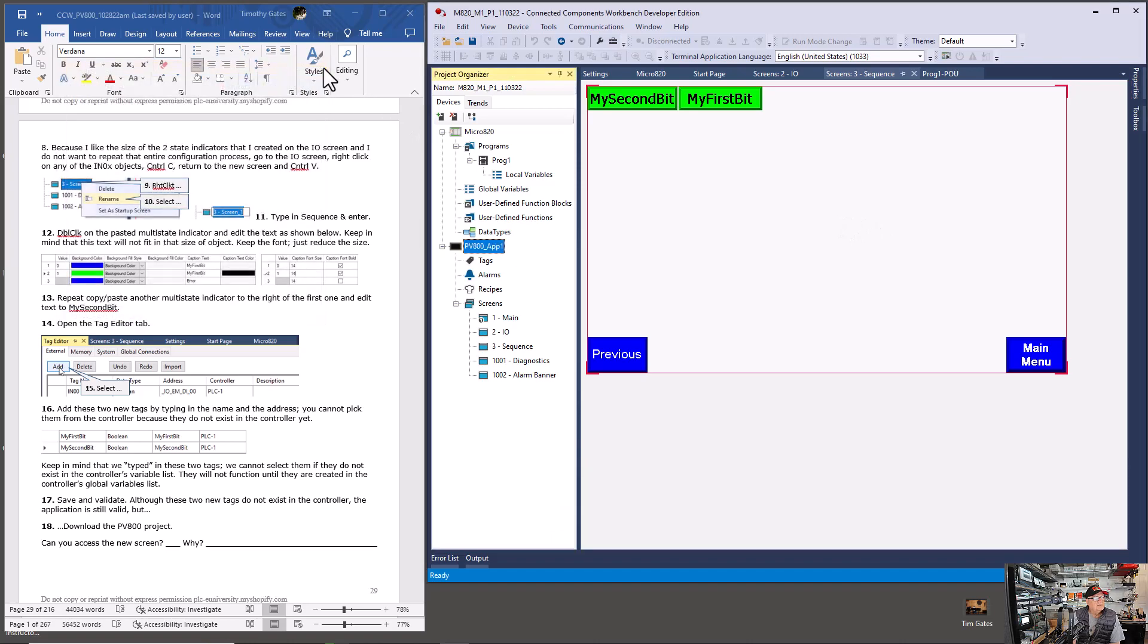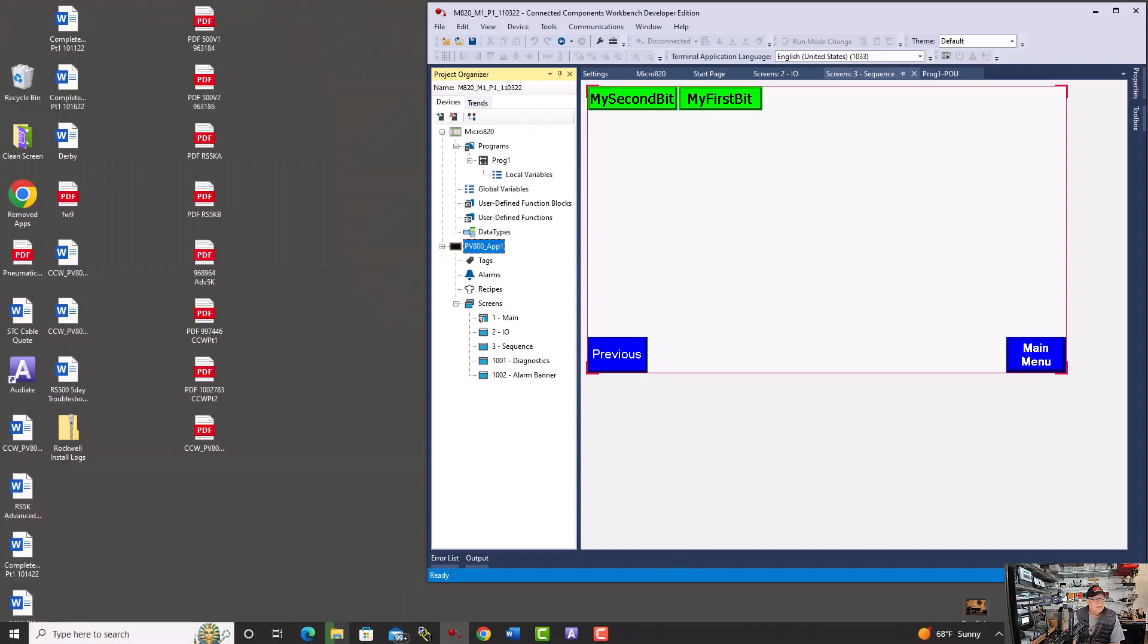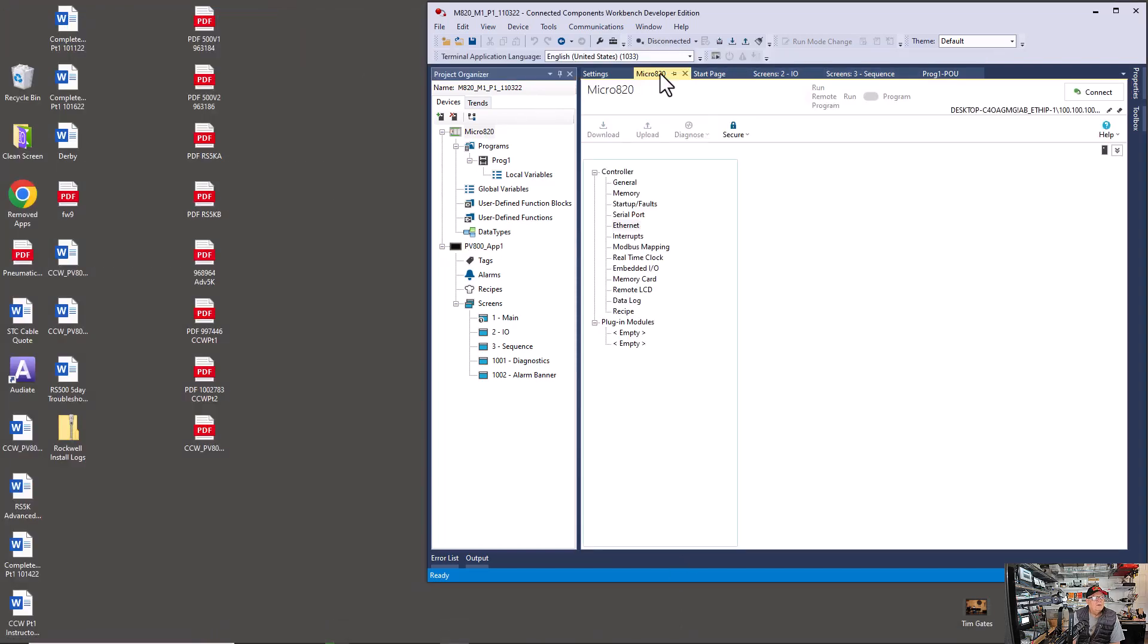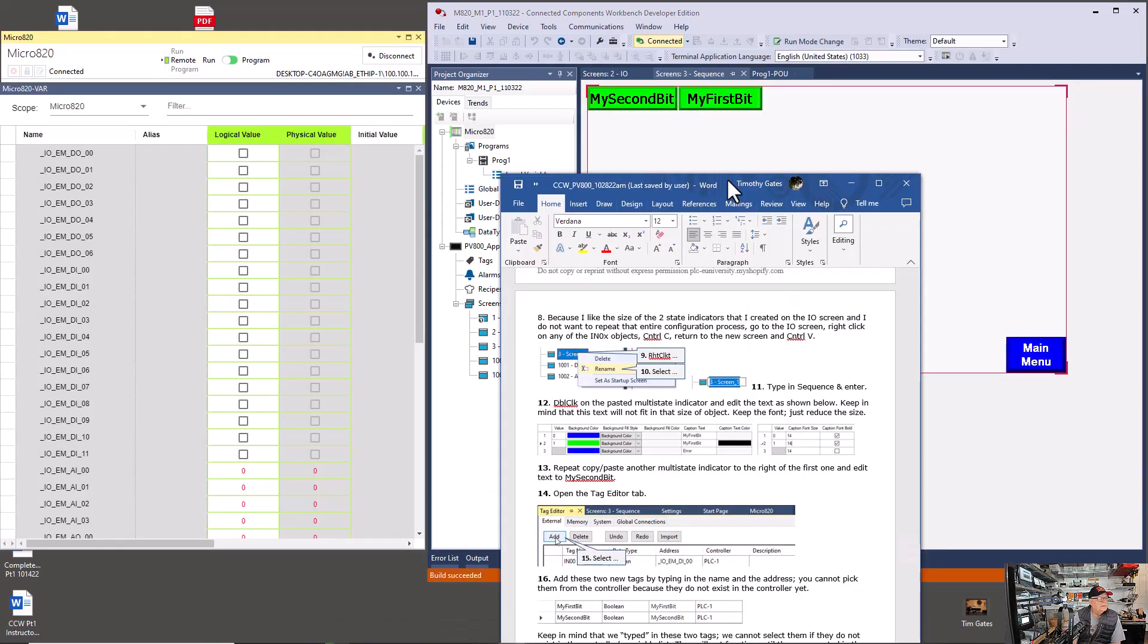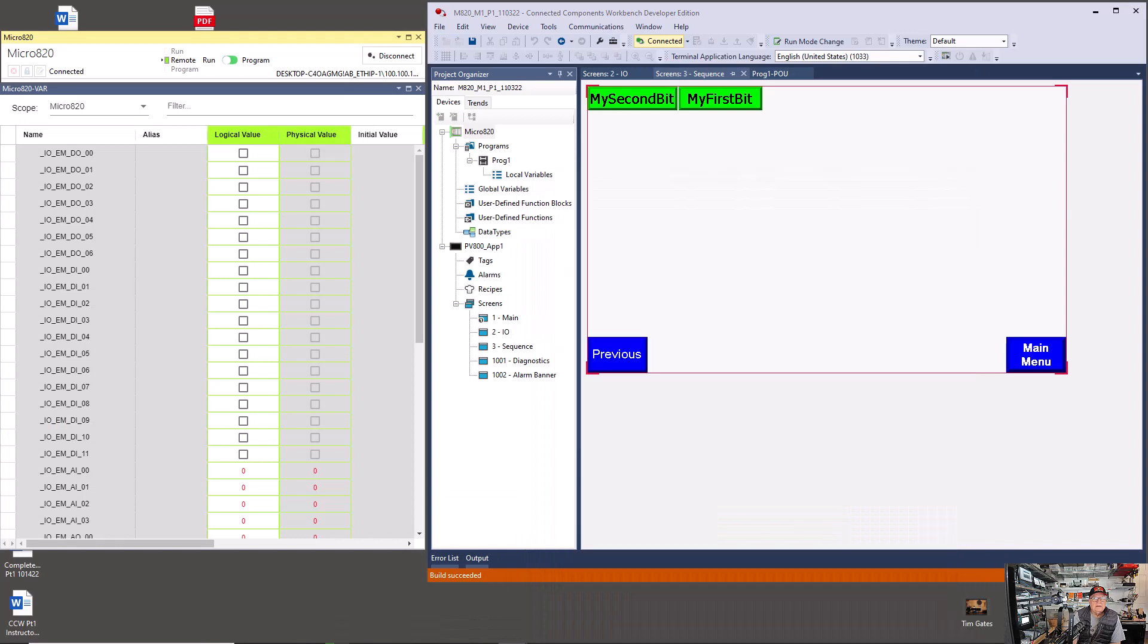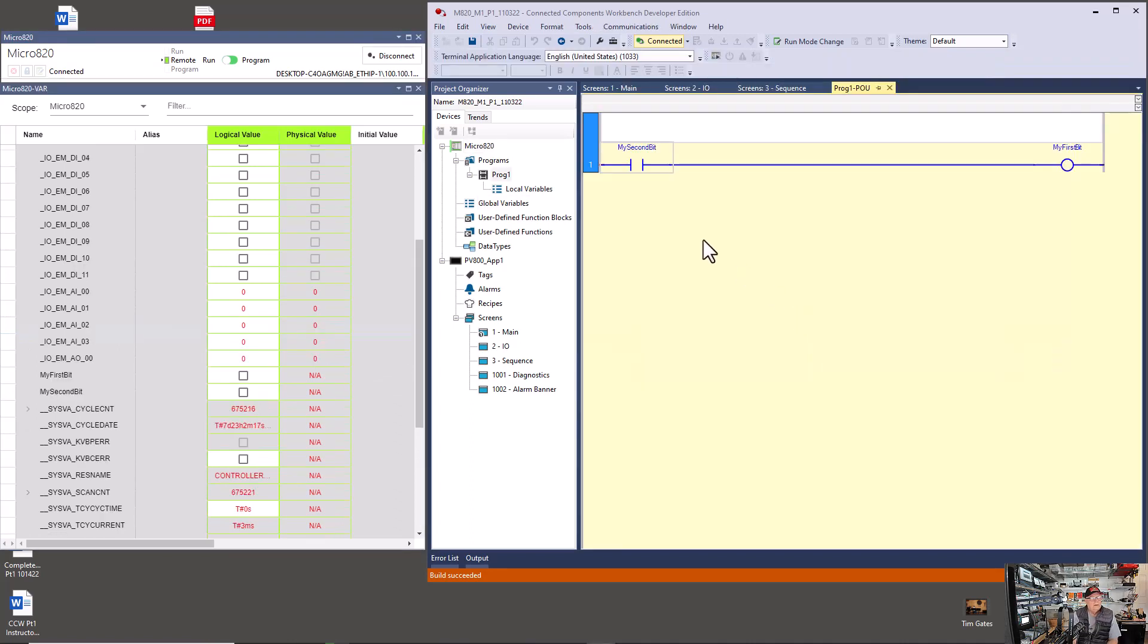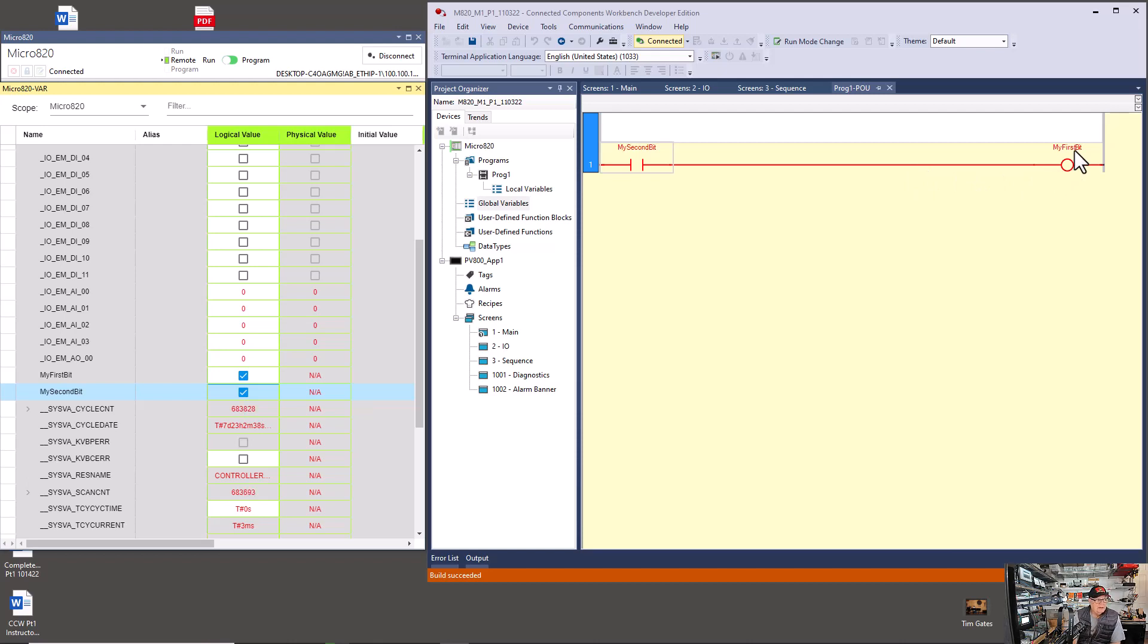I'm going to go back to the PLC. But in order to do that, I need, well, I lost that too. We're looking for that one right there. So I want to go back to the run mode. I could have just clicked up here on disconnected, then it would say connected. So I did not have to move that out of the way temporarily. So you can see over here and there's my first bit, my second bit. I'm going to first, I'm just going to click on my second bit and looking at our logic and looking at our database over here. First thing I'm going to do is click on my second bit. Of course, you see this went true, rung's true, turned on my first bit. And I'm looking at my screen, my actual hardware panel view screen, and it responded correctly.